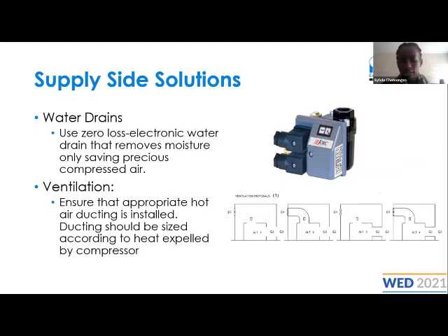So you can say, let me go and drain compressed air every 5 minutes or every 1 hour. But then the amount of condensate that has collected, let's say in June as compared to July, won't be the same. So incorporating an electronic water drain helps in the sense that it senses the amount of condensate within your system and drains only the condensate. It does not drain any compressed air. So that's why we have a zero loss electronic water drain. You will not have any losses in compressed air within your system, and it only releases condensate after it has reached a certain level.